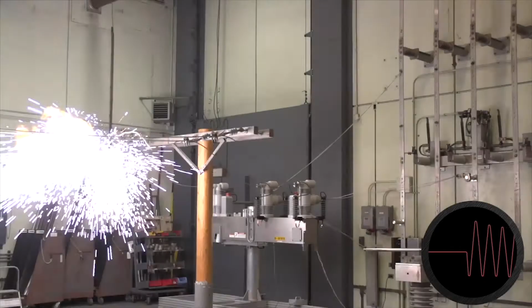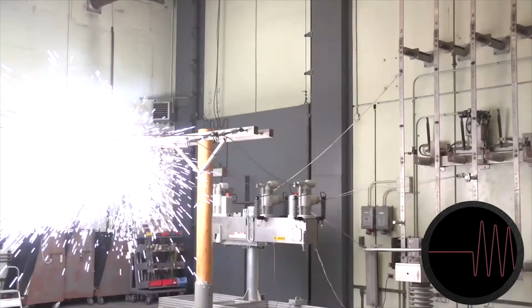Here's an example of a recloser closing on a fault with full force on the overhead distribution system. As you can see, the damage of reclosing with full force can be drastic. The more we stress our utility system, the shorter the life of its components and the shorter the life of the system altogether. Now demonstrated here is the IntelliRuptor using pulse closing technology to test the line for faults. It's clear to see how much smaller strain is put on the distribution system using this truly unique and innovative technology.